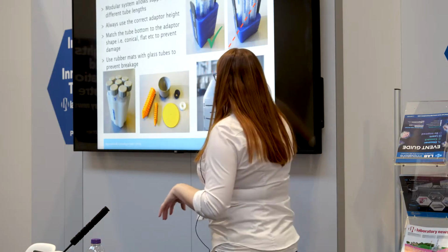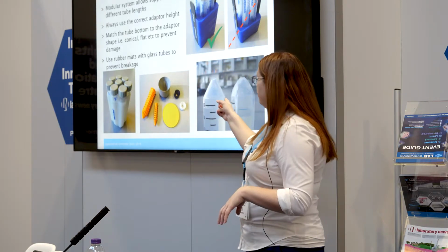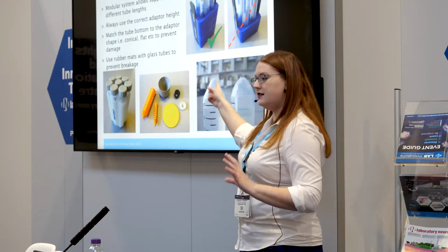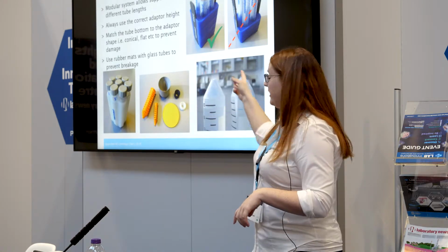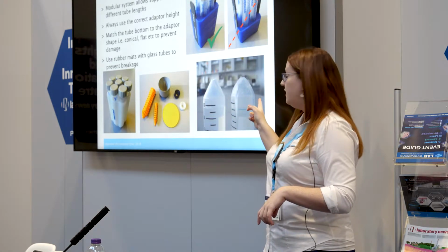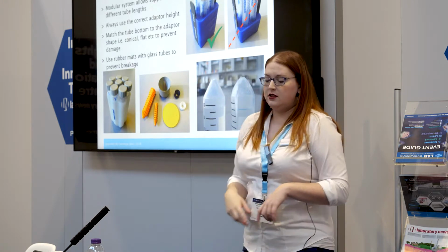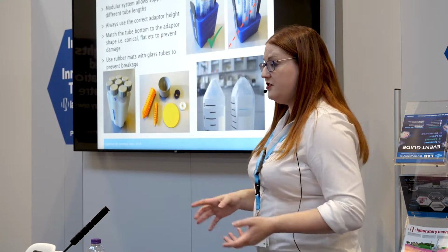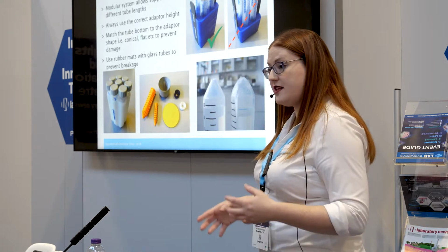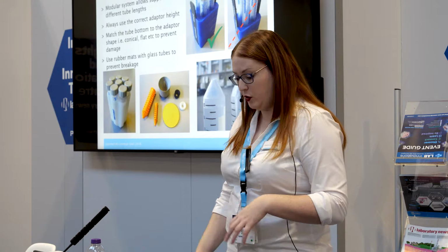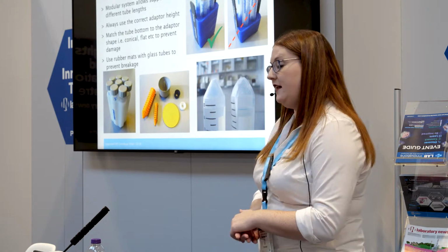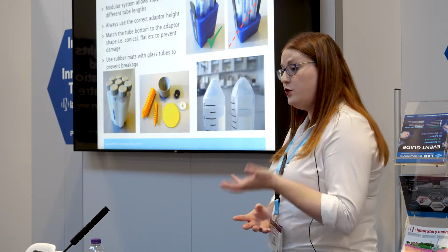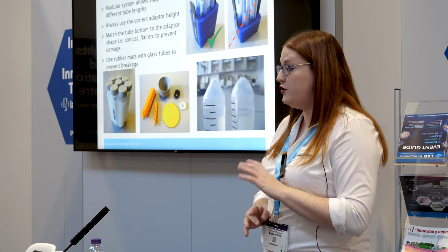This is to avoid things like this. So it's not the most obvious, but this is a centrifuge tube that's nice and fine. This one has been used without the supporting insert, and you can see it started to bow. Low speeds, this is not going to be the end of the world. High speeds, you're going to lose your sample because the tubes will break, because they're not designed to withstand those forces unsupported. This is particularly important if you're spinning glass tubes. Use the supports with the glass tubes because glass is not designed for it.